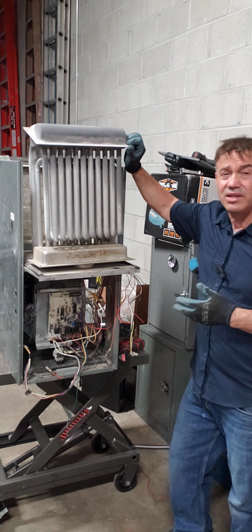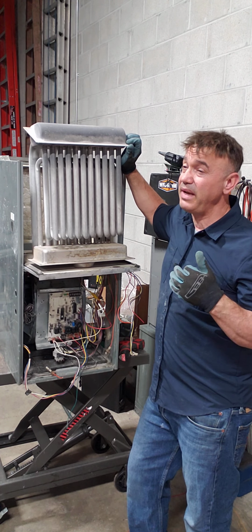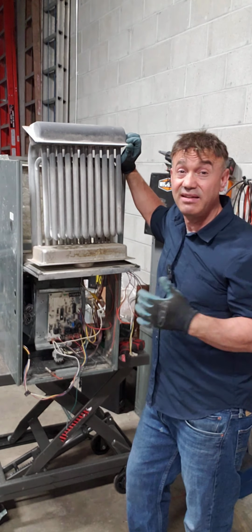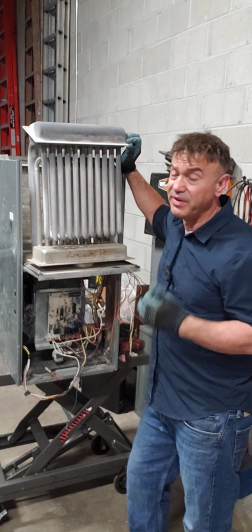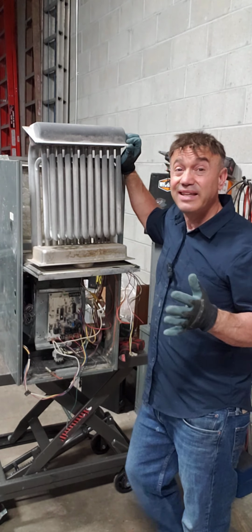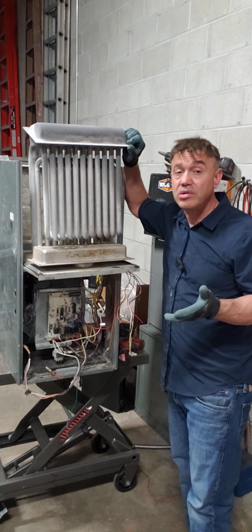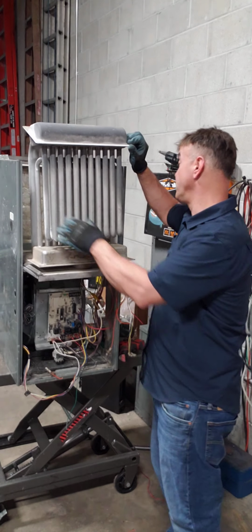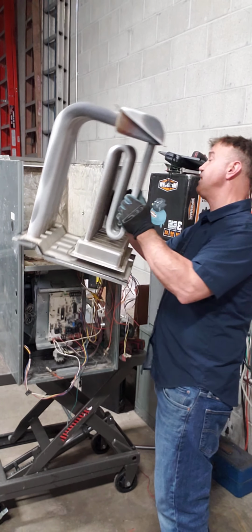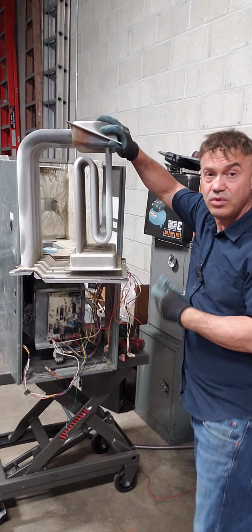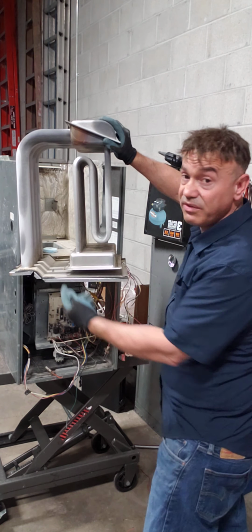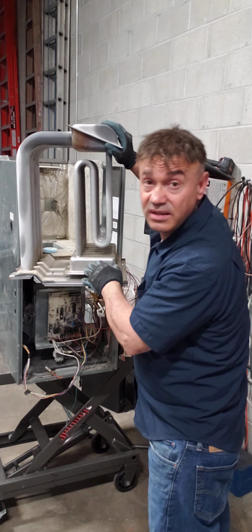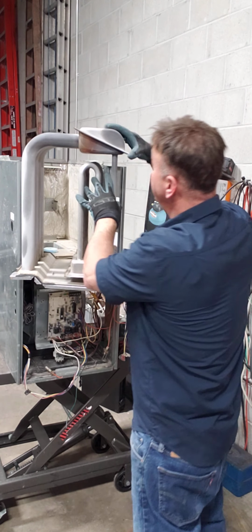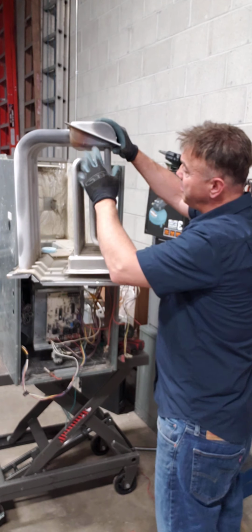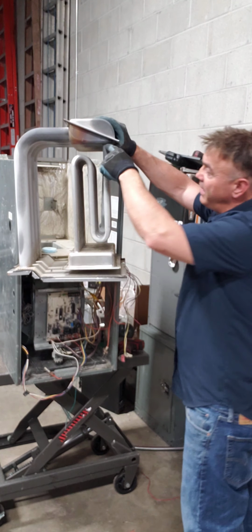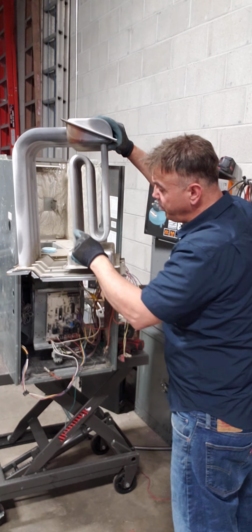Believe it or not, these heat exchangers are very expensive. Last time I changed one for a cousin of mine, it was a Carrier, of course, with a high variable speed modulating inducer. That heat exchanger was $3,800, but it was free because they have warranty. So keep in mind the way that Rheem designed the heat exchanger is so nice, so cute, so effective. The flame comes in here. Let me see, you can see it. Yeah, the flame comes in here, and here we have a mixing box. The flame is gonna be going all over the place, and then it will keep traveling into the tubular heat exchanger.